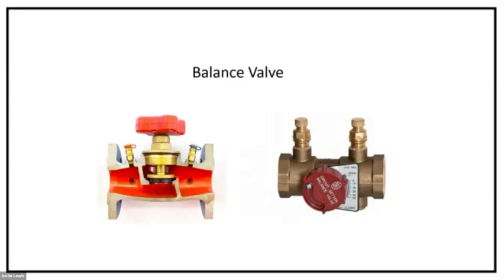Balance valves. This is an interesting one. So balance valves, we have test ports that we need to get access to, and typically we need about 3 inches of free space above these test ports. We need to make sure that insulation doesn't go over the entire assembly itself and leave us no access to find, let alone identify, what size the circuit setter is. We also want to make sure that we don't have control valve housings that are installed directly next to it with the housing covering the test ports. These are common issues that we want to get resolved before water's in the system and before ceilings are in place. It's much easier at this point than trying to deal with it 3 weeks before turnover.